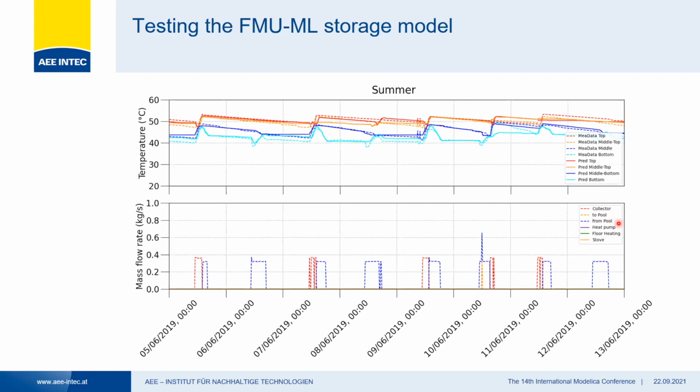Based on this component input, our model's predicted values show a good agreement with the measurement data during the summer period. And we can see that by introducing this P-load feature, we could capture the cooling behavior of the tank during the night when there's no load.